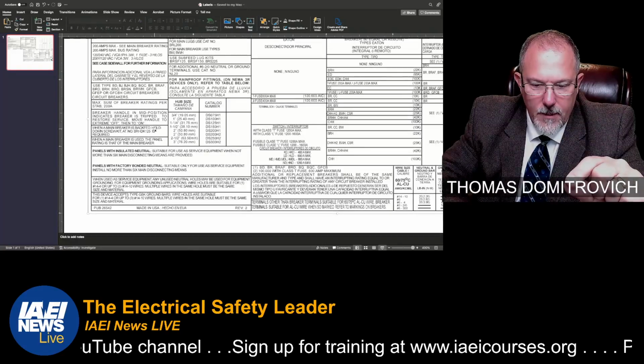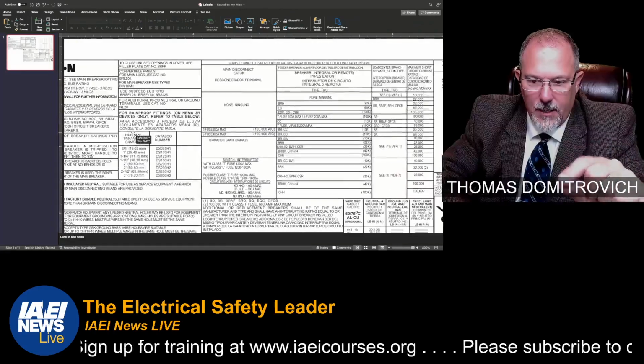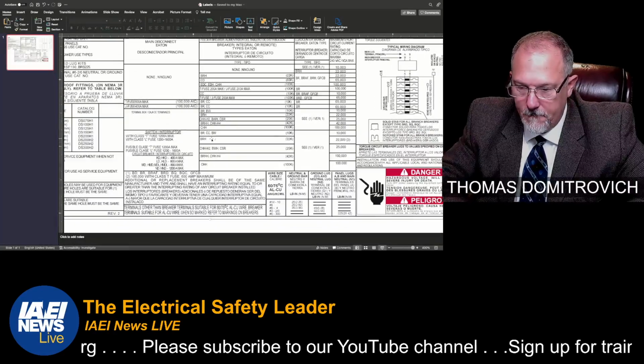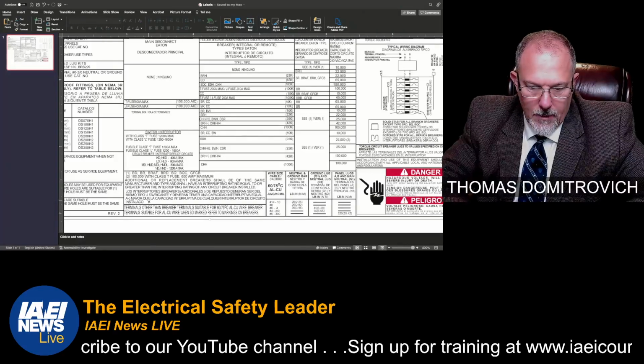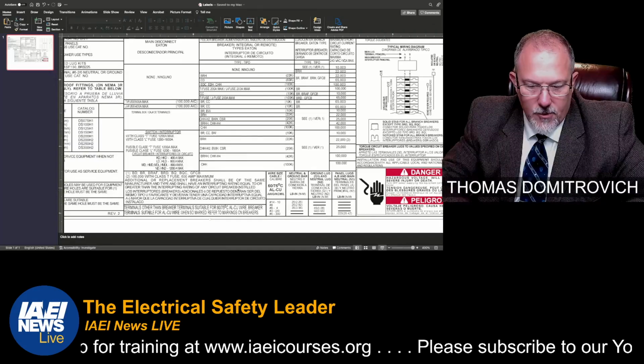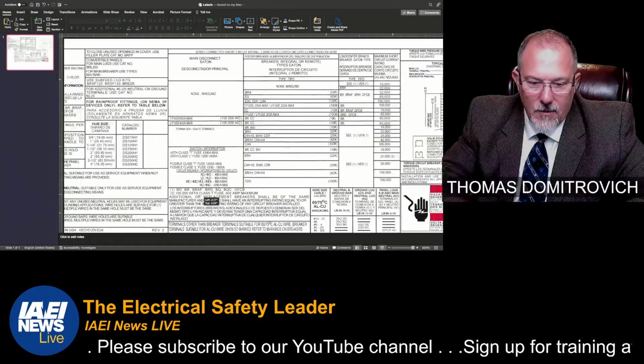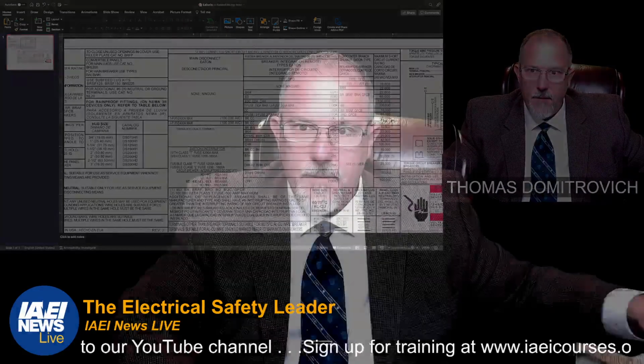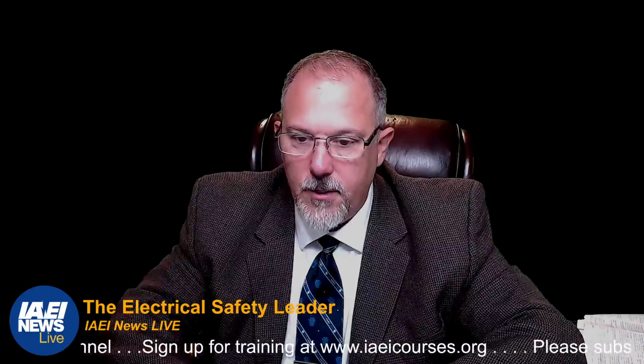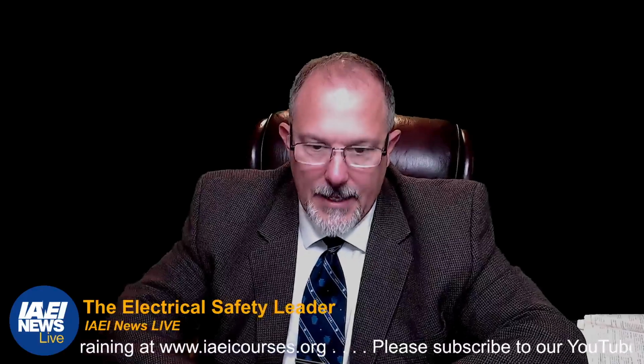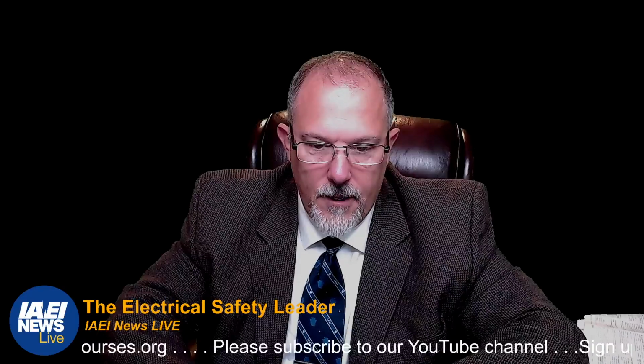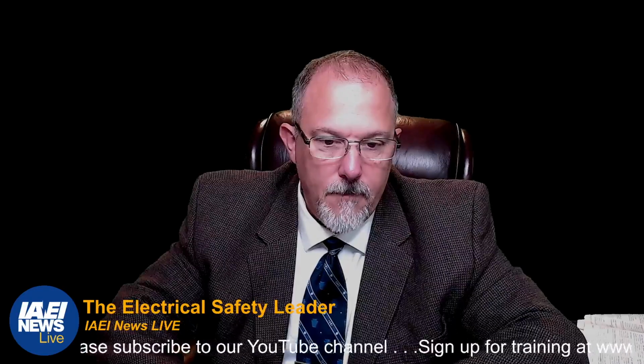Depending upon the breaker that I install inside of this panel will determine the short circuit current rating of the equipment. Additional or replacement breakers shall be of the same manufacturer and type, and shall have an interrupting rating equal to or greater than the interrupting rating of any circuit breaker installed. The lowest interrupting rating of any circuit breaker that's in this panel board, the lowest rating is the short circuit current rating of that equipment. That makes sense.